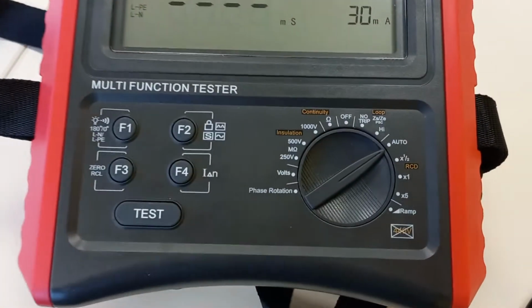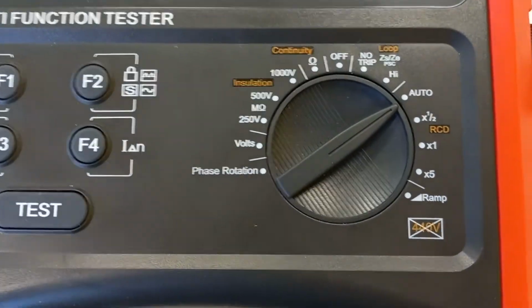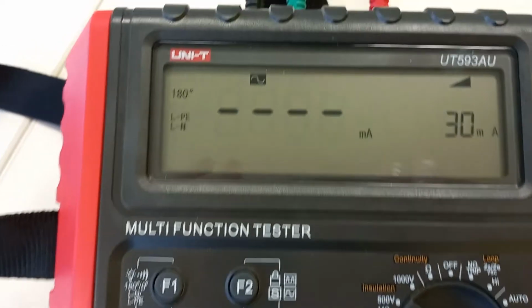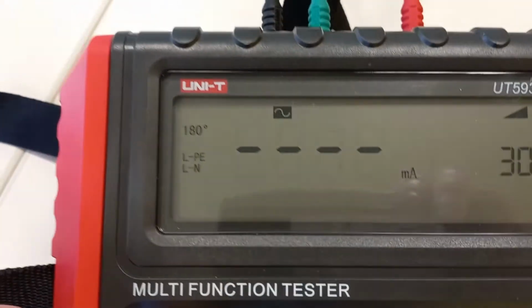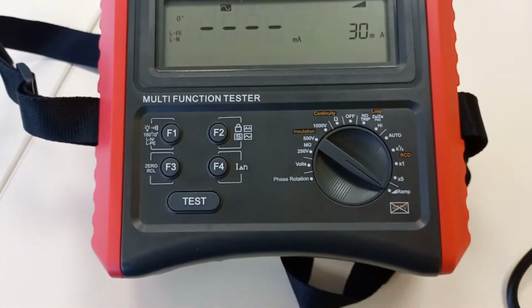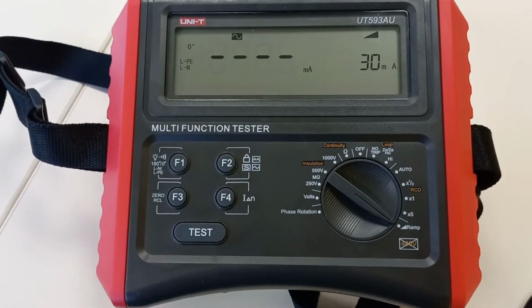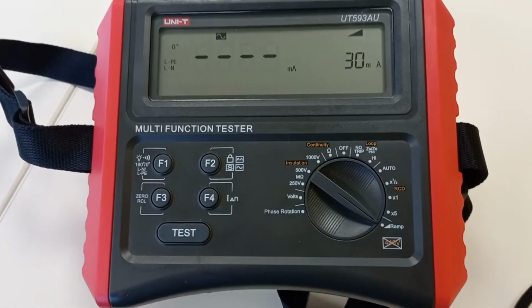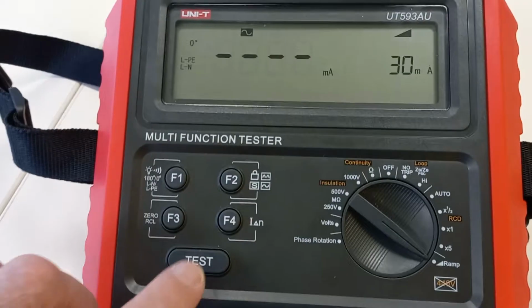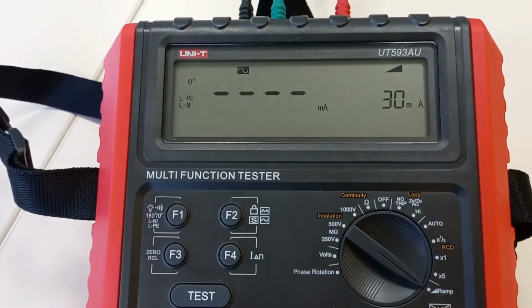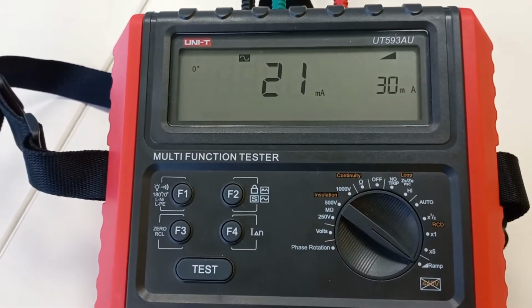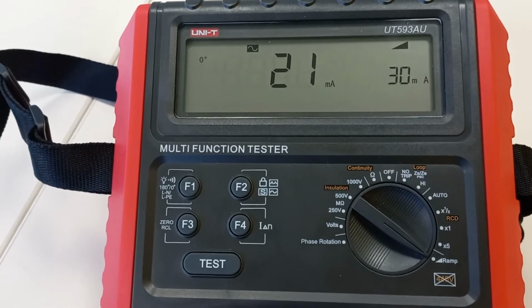The next test I'm going to show is the ramp test. I set this back to 0 degrees. This test is going to give us the leakage current that it actually does trip out at. So press the test function, and it tripped out at 21 milliamps at 0 degrees.